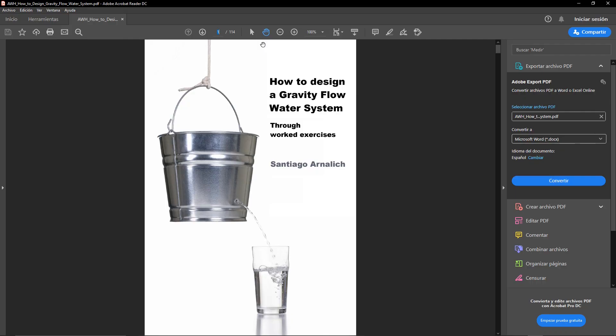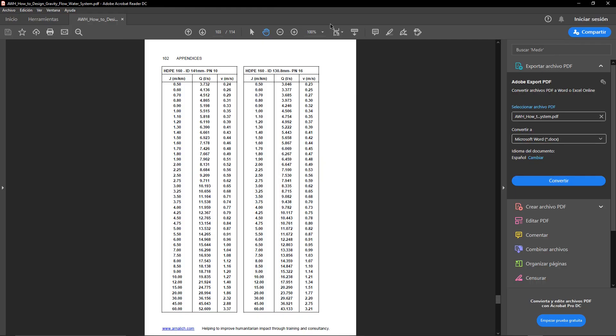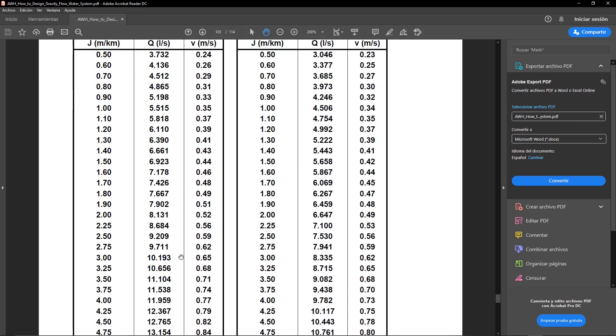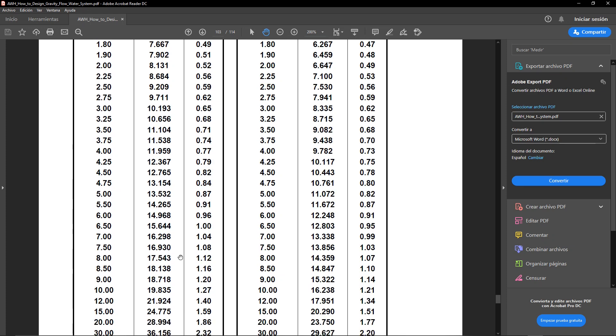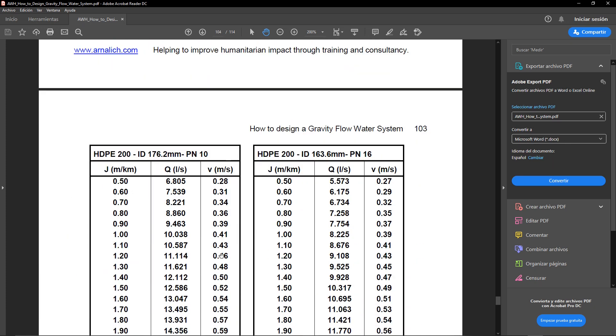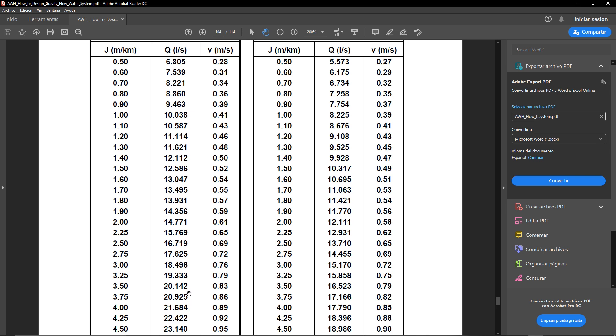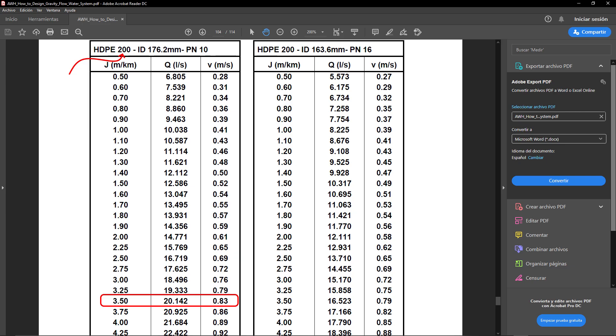Step 2 is to browse the head loss charts for our material of choice, HDPE and PN10, since the maximum pressure in the system is well below 10 bar. For 20 liters per second, a 160 millimeter pipe produces 10 meters per kilometer, too high. The next size up is 200 millimeters. 3.5 meters per kilometer is below our maximum 4 and we'll use this diameter.